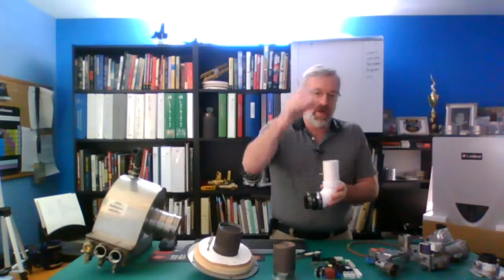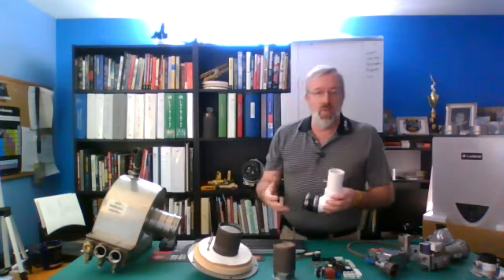It's a unique feature, because this pipes directly to the outside. As your atmospheric conditions change, this is going to adjust that gas valve for you, depending on the density of the air. So on a warm, dry day, it's going to be different than on a cold, wet day, or even a hot, wet, moist day. It's all going to change, and that's going to make those adjustments. We'll circle back to that air and how that's working in just a little bit, but I want to talk about some more stuff that's here.